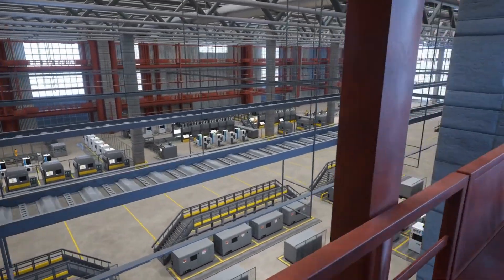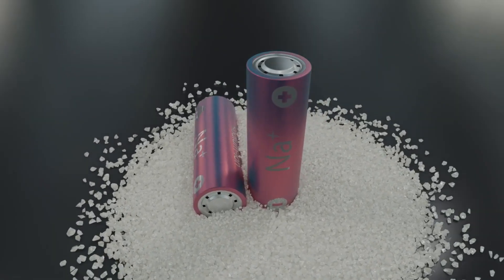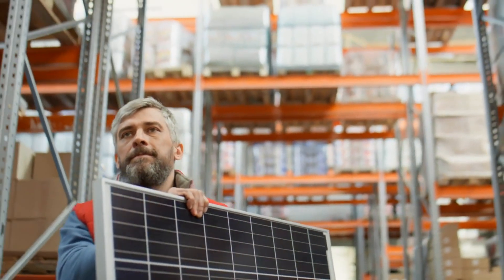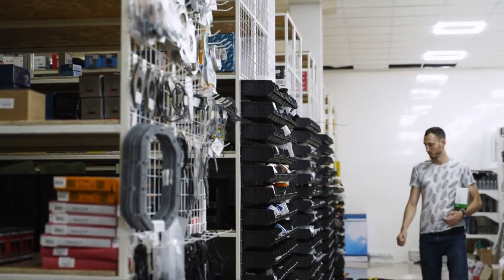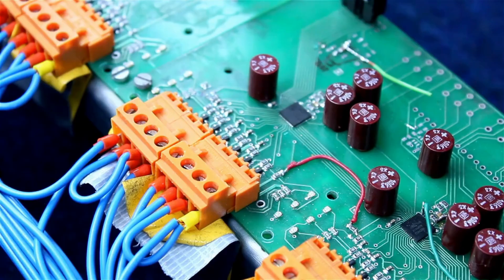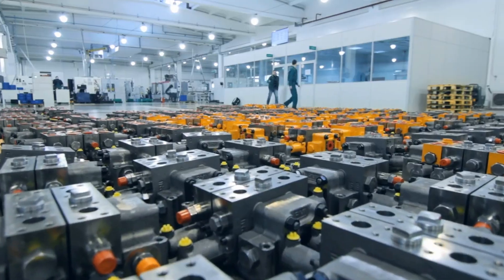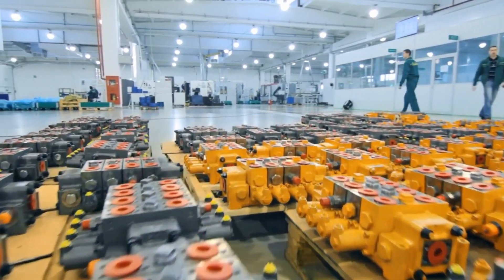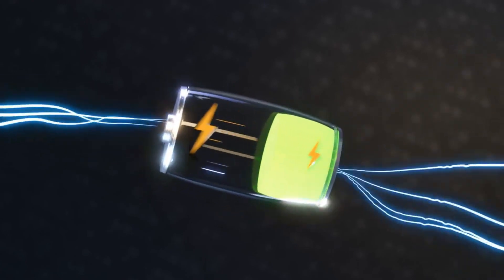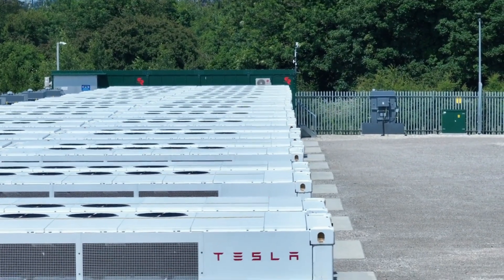So what about the downsides? The iron flow battery isn't as energy- or power-dense as lithium-ion batteries, meaning it can't charge or discharge as quickly. However, for stationary storage applications like grid storage, this might not be a big issue, and the need for more space can be offset by placing it under solar arrays. Another challenge with iron-based batteries is dealing with side reactions and proton imbalances — during charging, the positive side can become overcharged, leading to loss of protons and a rise in pH levels, requiring a proton pump to keep everything balanced. ESS has been working hard to solve these challenges, growing from a small team in a garage to nearly 140 employees with a massive facility for research, development, and manufacturing. Their iron flow batteries are currently at cost parity with Tesla's Megapack, and with a lifespan of up to 20,000 cycles, they offer excellent long-term value.